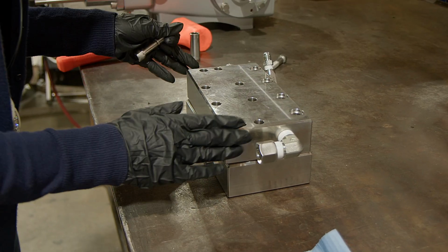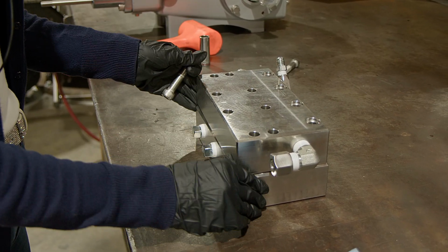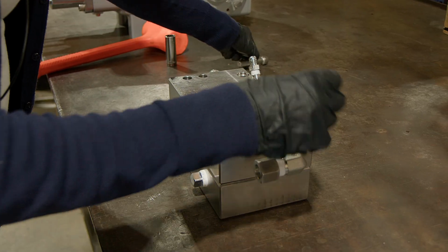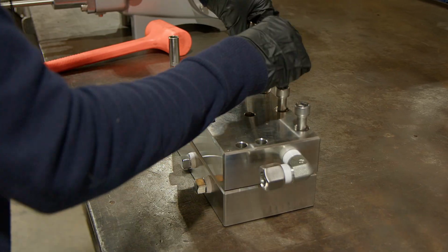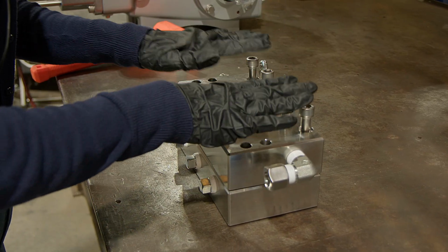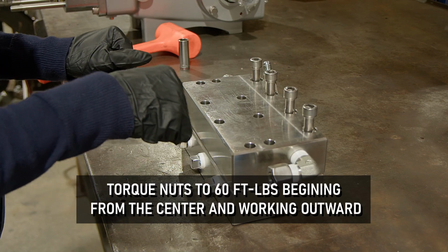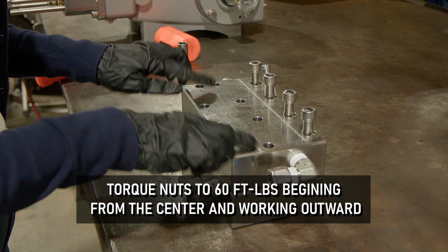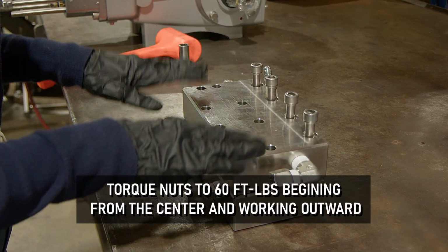Once you've replaced any of the internal components that need to be replaced, you're going to put your pump head back together. Put your Allen bolts back in, and torque these to 60 foot-pounds.